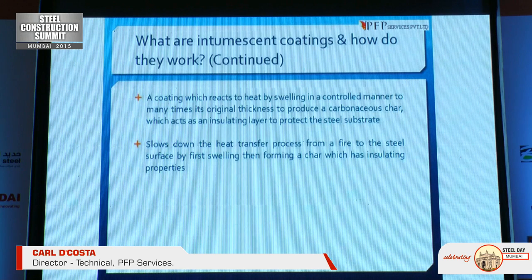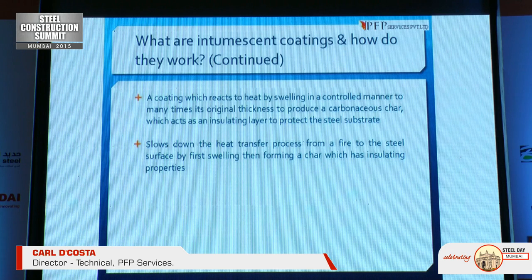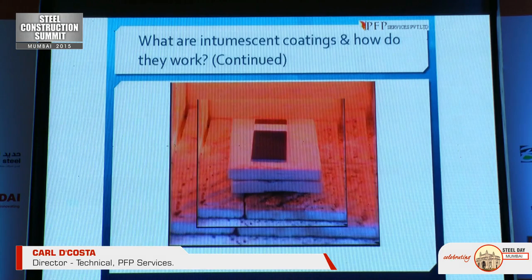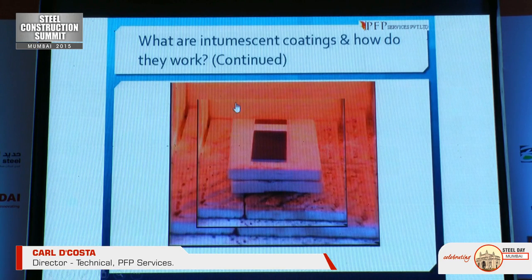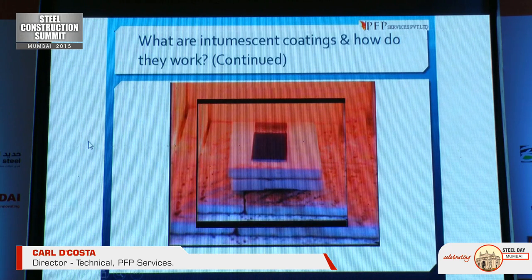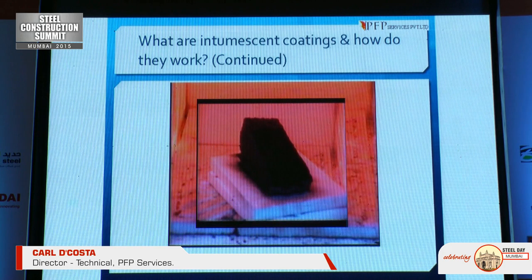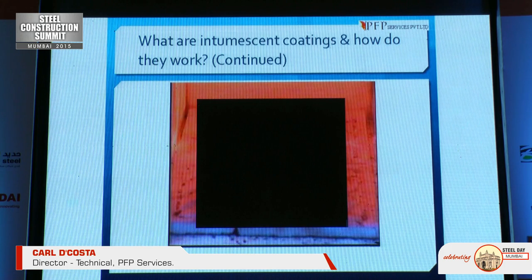An intumescent coating reacts to heat by swelling in a controlled manner to many times its original thickness to provide a carbonaceous char, which acts as an insulating layer to protect the steel structure. It slows down the heat transfer process from a fire to the steel surface by first swelling, then forming a char with insulating properties. It expands approximately 60 to 70 times its original thickness.